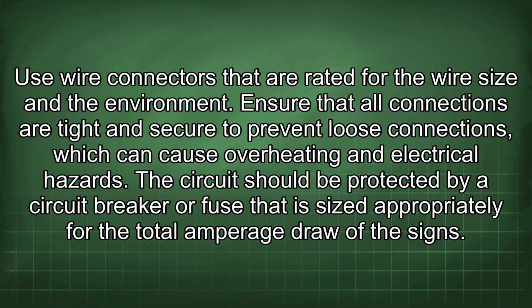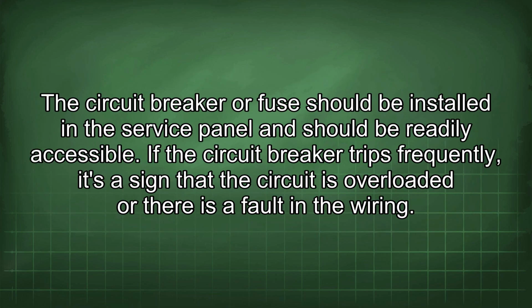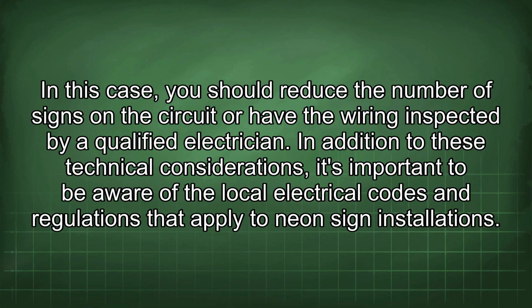The circuit should be protected by a circuit breaker or fuse that is sized appropriately for the total amperage draw of the signs. The circuit breaker or fuse should be installed in the service panel and should be readily accessible. If the circuit breaker trips frequently, it's a sign that the circuit is overloaded or there is a fault in the wiring.